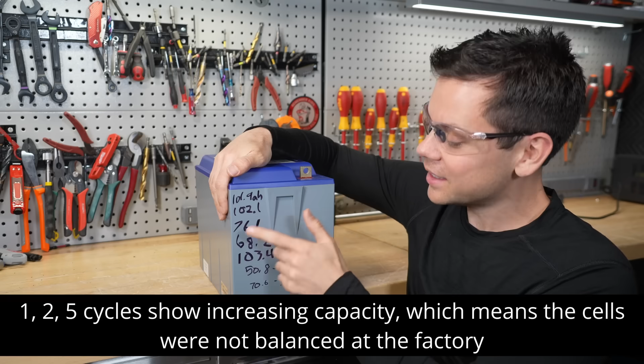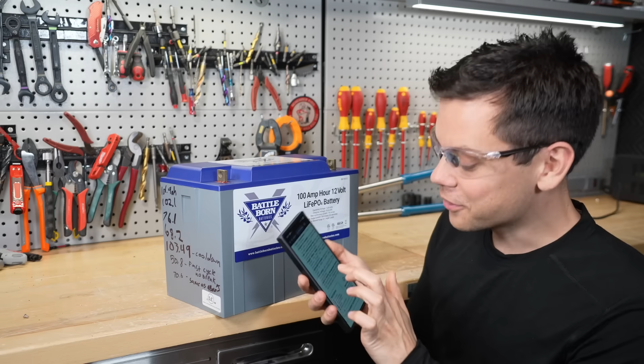It disconnected short. Now, if this is certified to a UL standard, how did they not catch this? It's rated on the sticker on the battery for 100 amps, but I can't pull that. And I'm getting consistent results, there's no surprises here. Take your own Battleborn if you have one and do this test. I really want to cut into it, but we need to get more cycles on here, so I ordered a cycle machine so we can put 100 or 1,000 cycles on this. This thing's rated for 3,000 to 5,000 cycles.